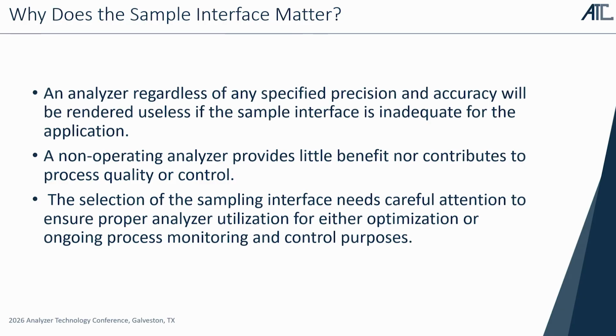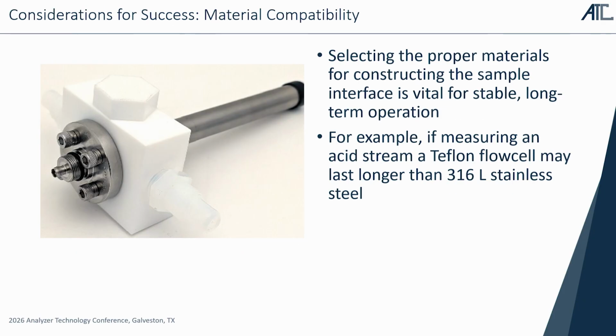So what this talk is really about is all the careful consideration that needs to happen when you're going through the proposal piece, whether you're a process engineer, whether you're a tech that's looking at doing some maintenance, or whether you're like a system integrator trying to pull together all these pieces from different vendors. One of the easiest ones to keep in mind is material compatibility, right? Code of construction requirements. If you're doing an acid, you probably don't want a 316 material. You might want something like a Teflon flow cell, right? Because the Teflon's gonna handle those acid conditions. Maybe you want a C276 Hastelloy probe. Everybody gets this. We usually don't mess this one up.